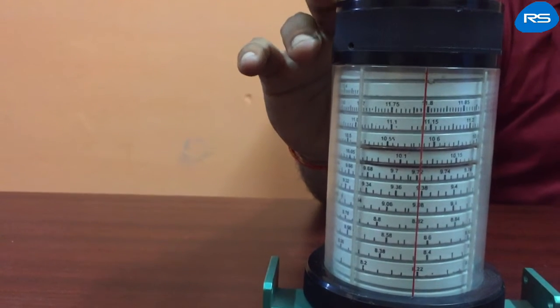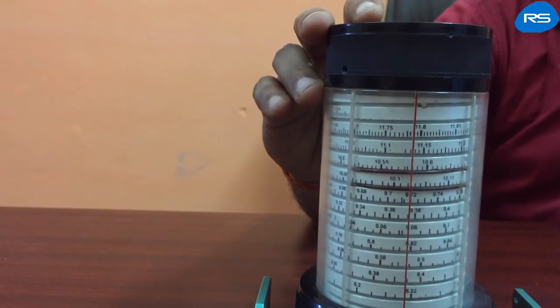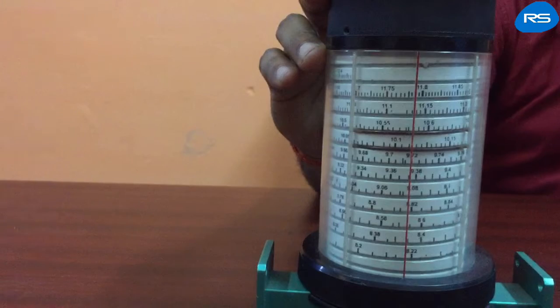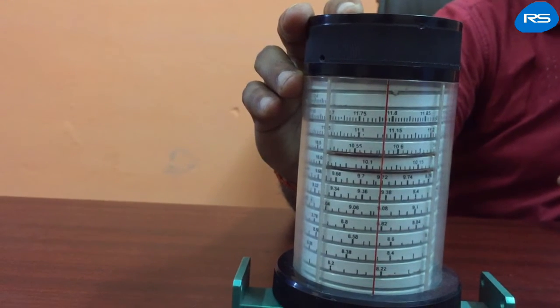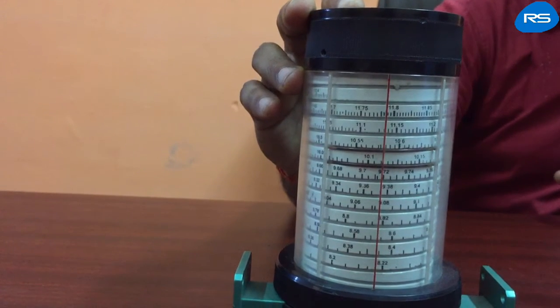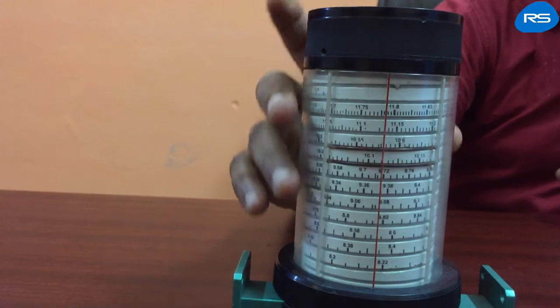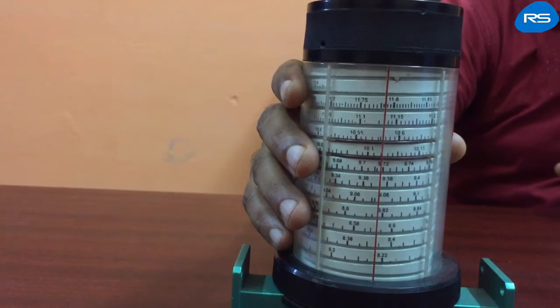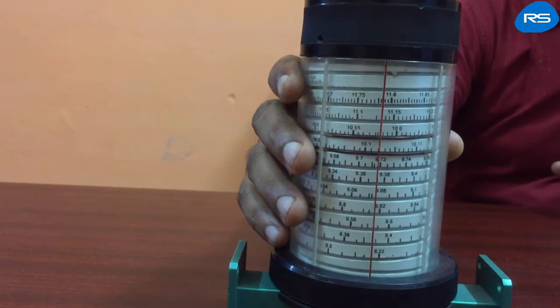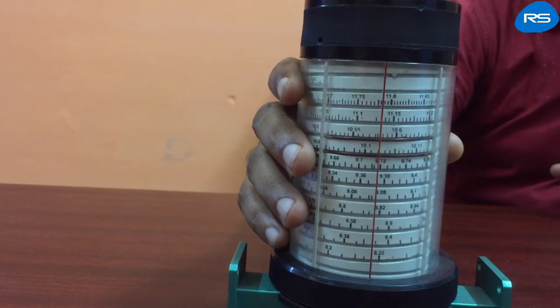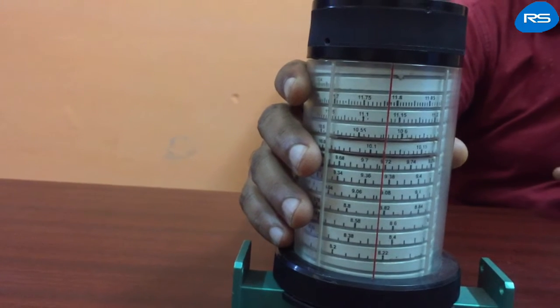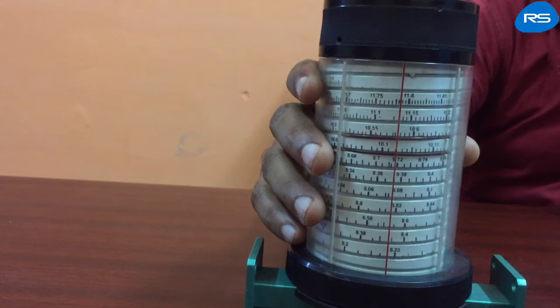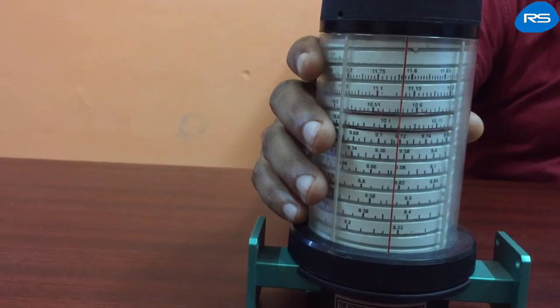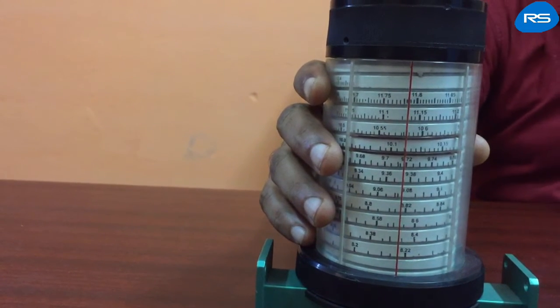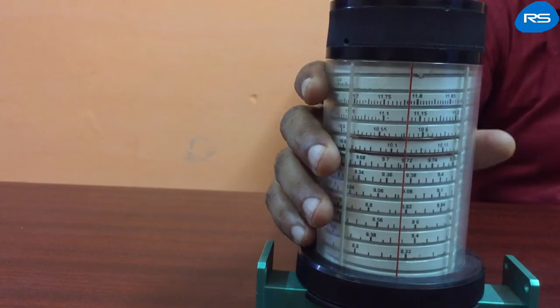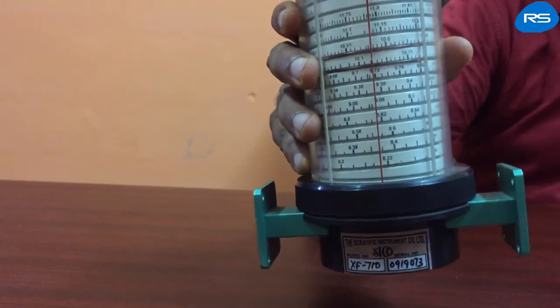The tuning can be calibrated in terms of frequency by known frequency input signals and observing the dip in the display unit, power meter, connected at the output side of the waveguide. The accuracy of such a wave meter is in the range of 1% to 0.005% for available quality factor of 1000 to 50,000 respectively. Since the power is absorbed in the wave meter at resonance, this is called absorption type wave meter.